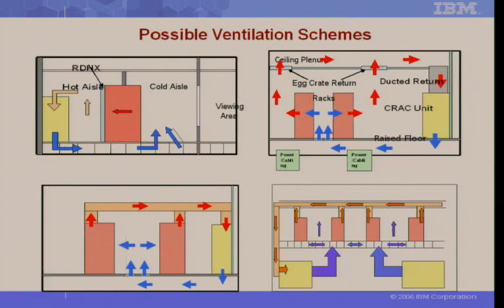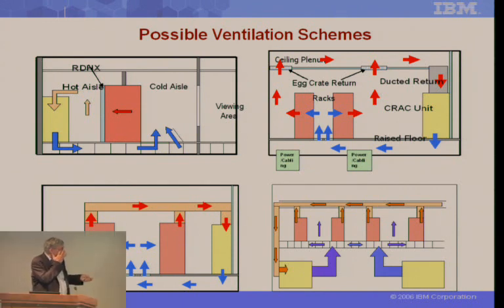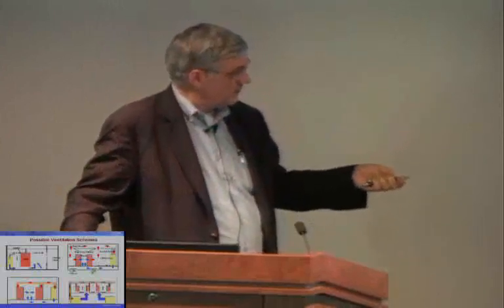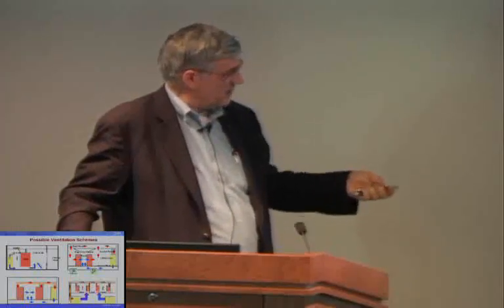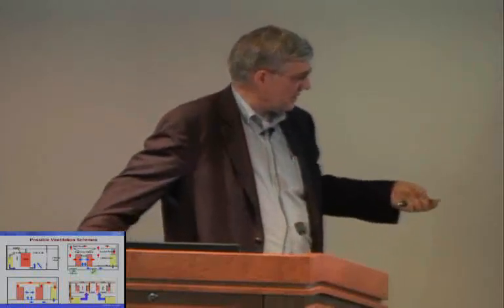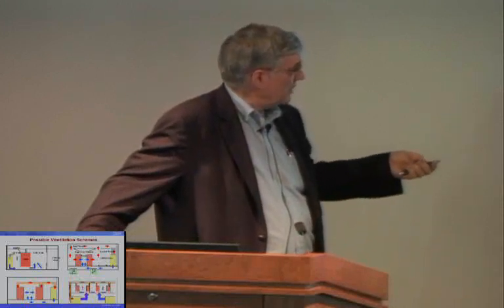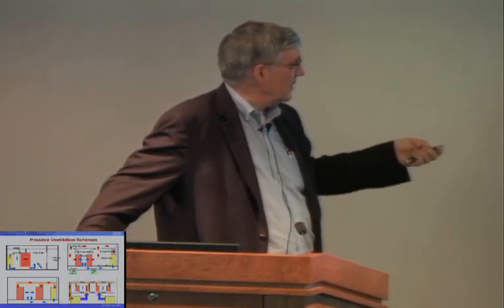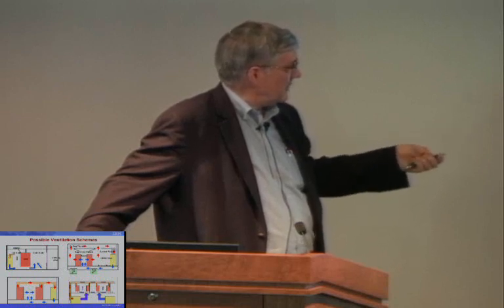Not everything is going to be liquid cooling, so there's a lot of air cooling designs out there on how to design this into data centers. This is kind of the typical setup where you come into the cold aisle. The fronts of the machines face that cold aisle, the cold air washes the fronts of the machine, goes out the back, and then back to the CRAC unit, which is the air conditioning unit. That's a typical setup, but there are more ducted flows and various baffling that may occur. Here's a rear door heat exchanger that takes out a major part of the heat load.